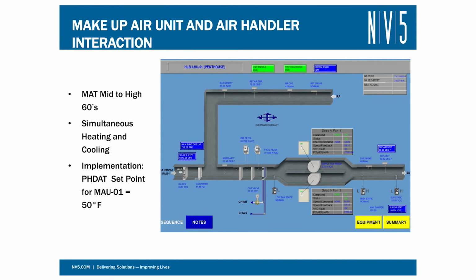So next we have the makeup air unit. This is a unit that feeds air into those two air handlers we talked about earlier. This one had a preheat discharge air temperature set point of 53 degrees. So that was what was controlling that. If I can do this clicker, that reheat coil or preheat coil. By the time it got out to the units, we were seeing about 55-degree air. We recommended that that be changed to a 50-degree discharge air temperature set point.